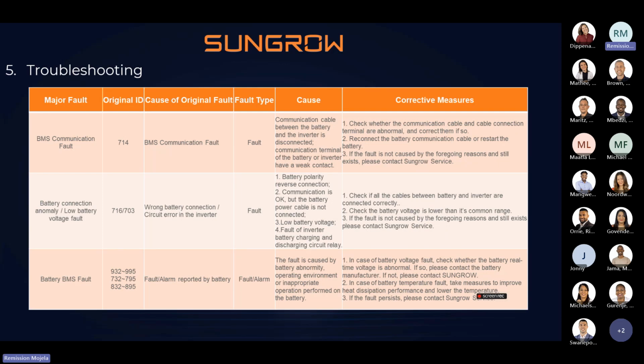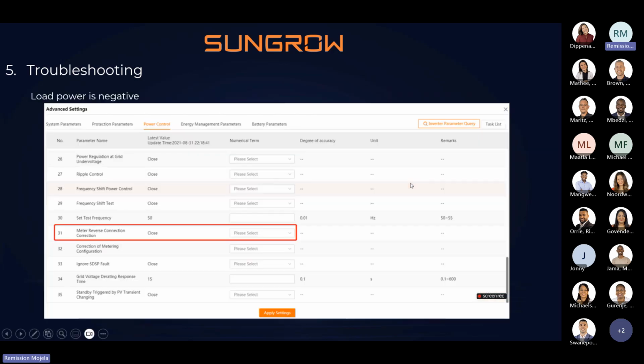The only thing that I normally explain in this part is that we have alarms and then we have faults. With alarms, the system will work just fine, just like these ones. The inverter will work with PV and the grid, but if the grid falls off and the PV is not sufficient, the inverter will switch off. But the inverter will work just fine with these ones. It will be producing power from PV with all the alarms, by the way.